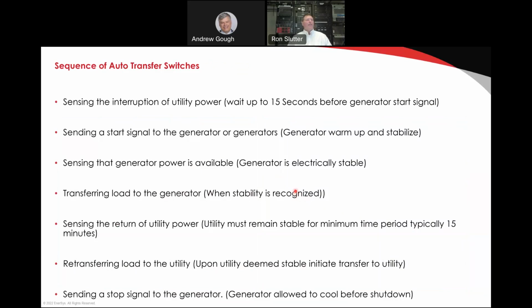So now let's talk about the sequence of an automatic transfer switch and make sure that you understand how these work. First of all, we sense the interruption of utility power. And do we instantly start the generator? The answer is no. We wait for some period of time, most likely around 15 seconds, because what are we on when we're waiting? We're on battery. We've got plenty of battery capacity. We have 2 hours of battery, and most people have at least that. So 15 seconds, no problem. We just let it ride through on battery.